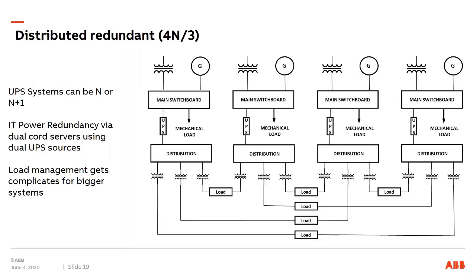The other one we see is what's referred to as a distributed redundant system, which is similar in some ways to the catcher system I showed. I also show this one with 4 UPSs, and of course in both of them I show 1 UPS, but this could be 2 UPSs in parallel or 3. And each UPS here could be 2 or more UPSs in parallel. Actually, very popular right now for both configurations is a total UPS capacity of about 2 megawatts, and that could be 2 1-megawatt units in parallel or equivalent.